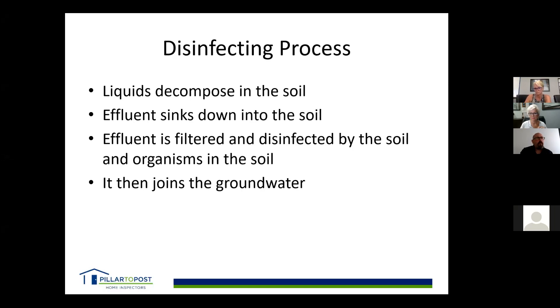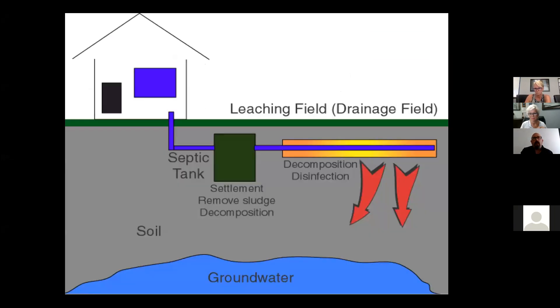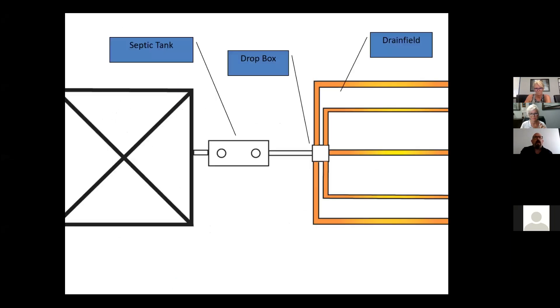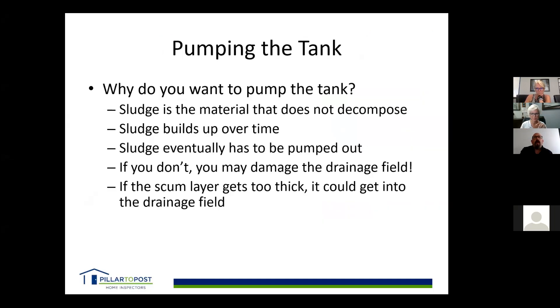We need to clean the tank, and the most common question is: how often? The reason we need to clean it is that solids settle to the bottom. Organics will decompose over time, but inorganics won't, and that sludge layer will build up. If we don't pump it out, we'll end up sending sludge or solids out to the field bed, which will cause it to fail.